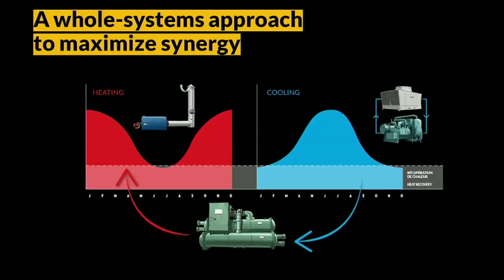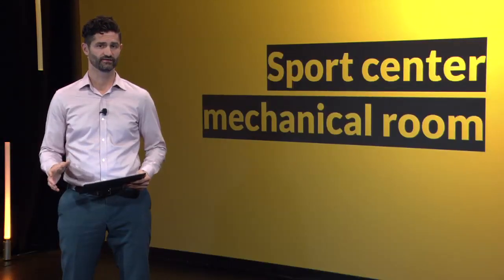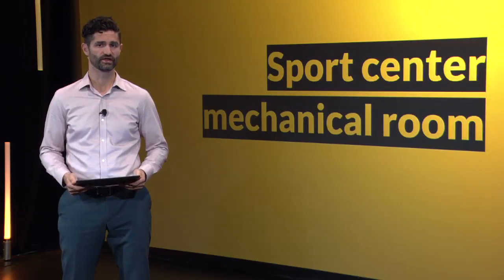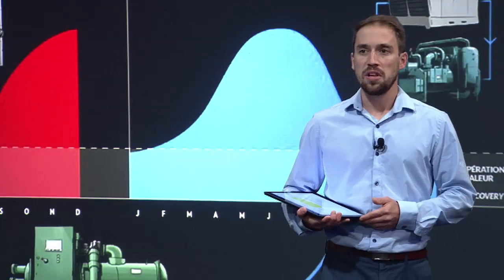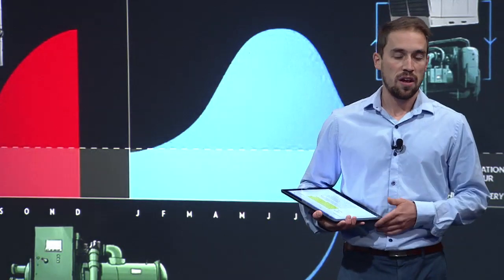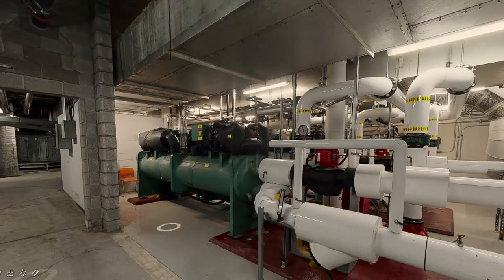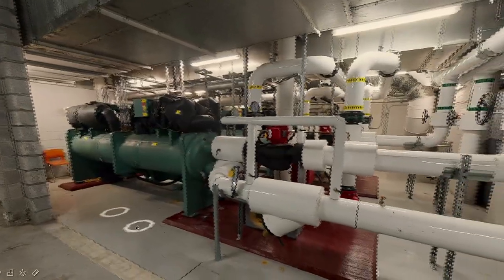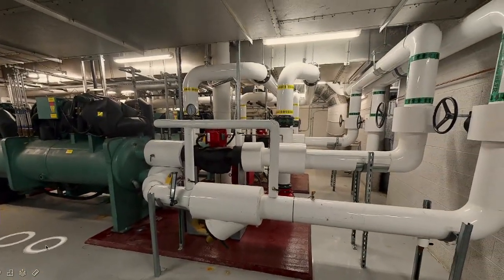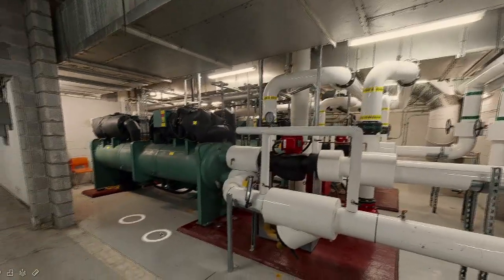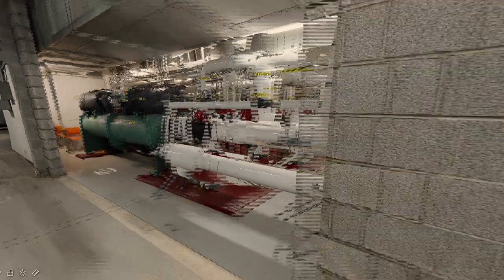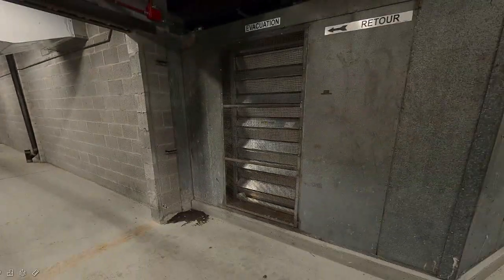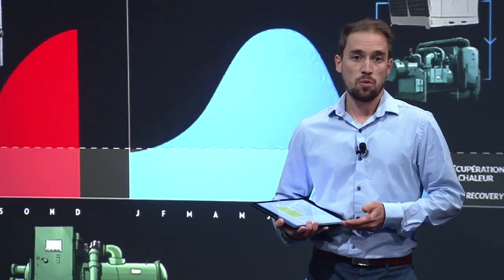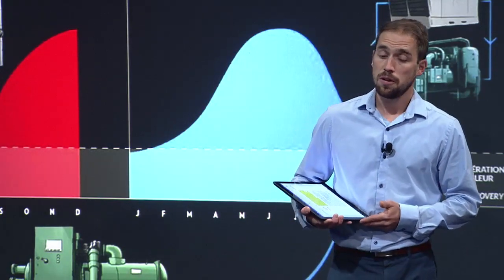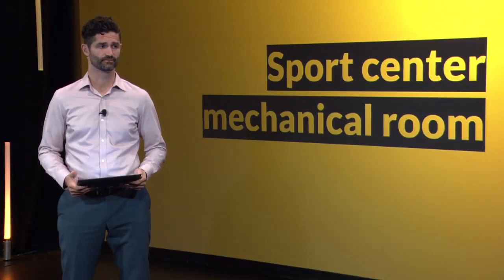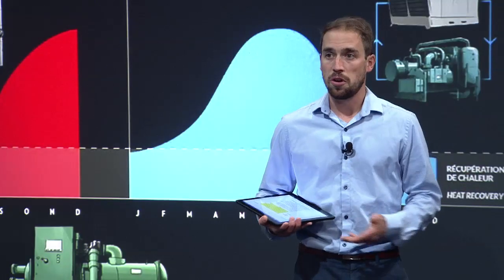Give us a sense, Simon, of the steam load in summer before the project, and the heating load that the heat pumps carry alone now. Before the project, we had around 10 million BTU per hour, so around 10,000 pounds per hour of steam working in summer. After the project, we now use around 3 million BTU per hour. So there's around 7 million BTU per hour that was just heat losses through the steam system, just from keeping the steam system, the deaerators, and other components running.